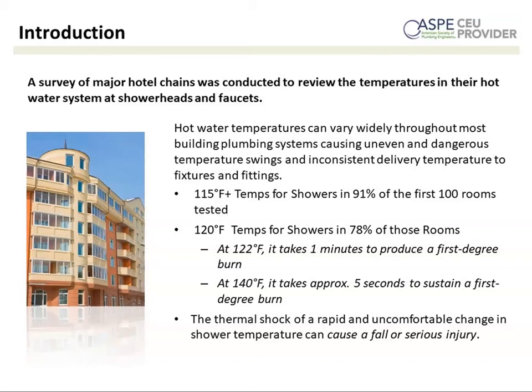So there's the risk of obviously scalding, and then there's the risk of thermal shock, which is a sudden change in water temperature. It could be hotter, it could be colder, that results in someone within a shower falling or stumbling, and that fall can cause a serious injury. So again, these are real life examples, and the way these temperatures were taken was we'd go into a facility and measure the temperature at the shower and the faucet by turning the handle to the full hot position and recording the maximum temperature. So as you can see, many facilities at the point of use are running very warm temperatures.